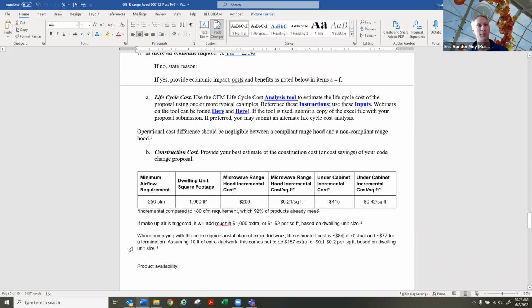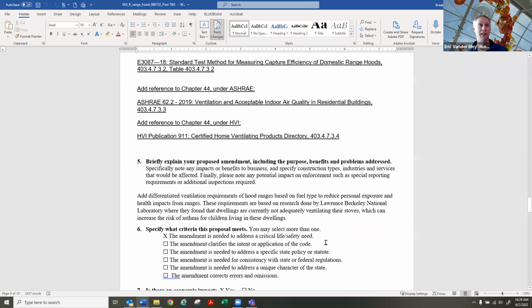To start triggering makeup air, unless someone on the TAG chooses to try to modify this proposal today to lower that threshold. What we did try to add was awareness around the testing: if you're required to have makeup air, you have to have an automatic system. And if you are exempt from makeup air, then you need to either test with the window manually opened, or you can try to test with the window closed and see if you can achieve your minimum airflow. So there is some direction in the testing section now to draw attention to this.